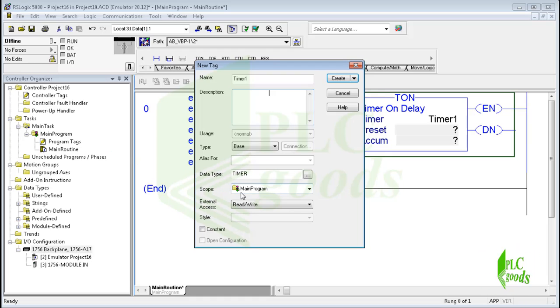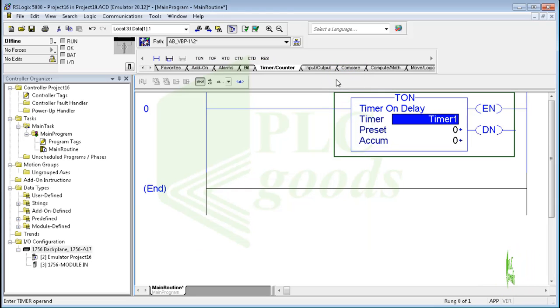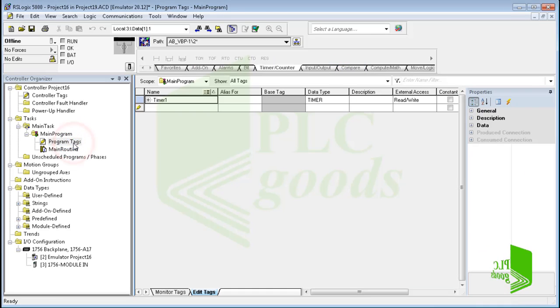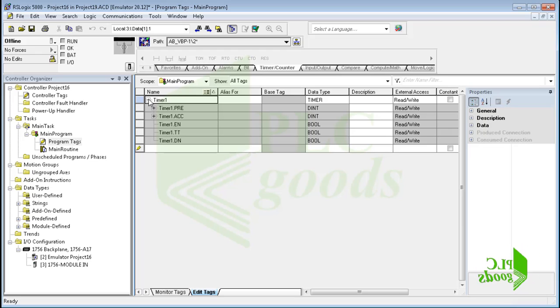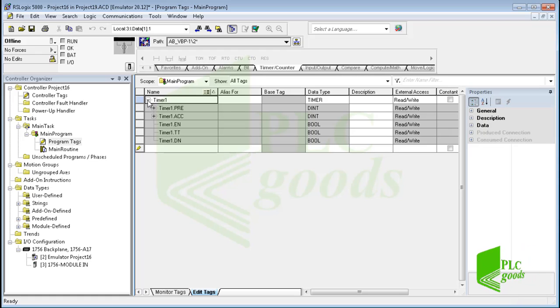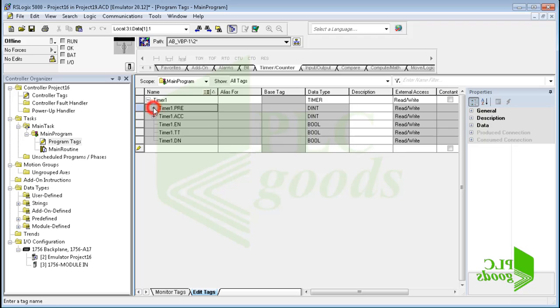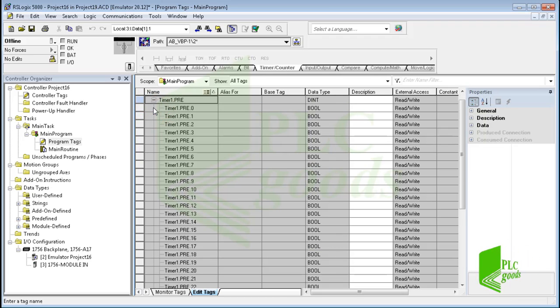The tag has been created. If you remember, the timer address in RSLogix 500 software is a data table address or symbol, whereas the timer address in RSLogix 5000 software is a predefined structure of the timer data type, but their parameters and status bits are similar to each other. The first parameter is the preset value, whose type is double integer, so this parameter uses 32 bits to store a desired time. Note that the time is stored in milliseconds.